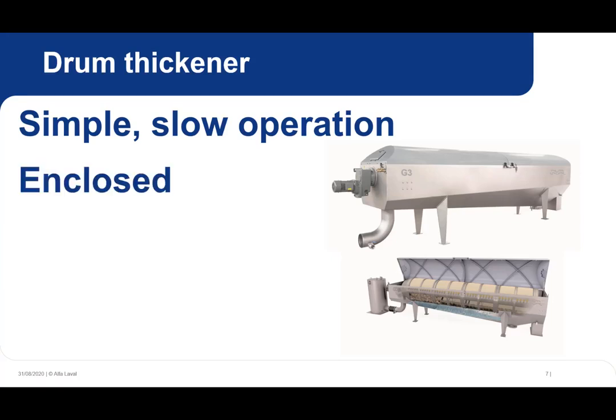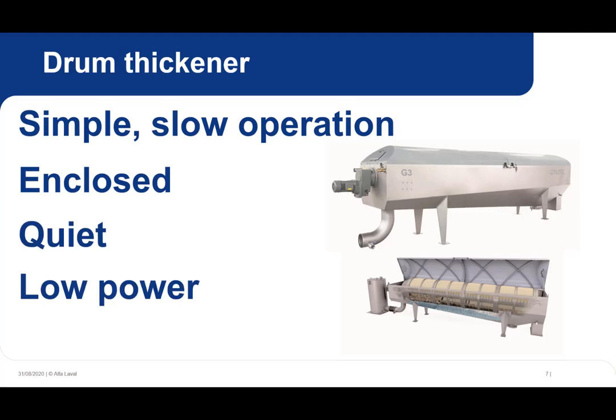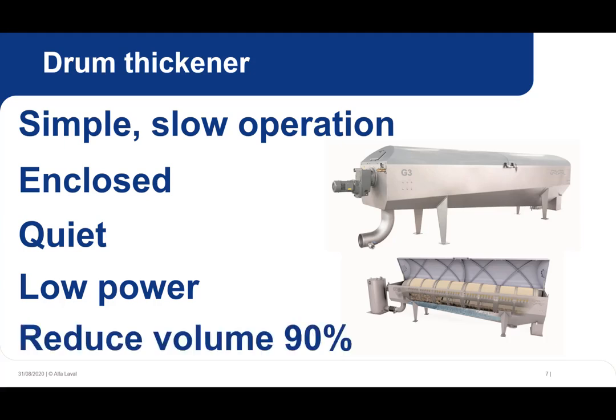A fully enclosed design means that a drum filter will be better at containing odor and can be installed outside if necessary. It runs quietly and has low power requirements. Thickening performance can be adjusted by varying the feed rate, the polymer type and dosage, the drum speed, and the spraying interval. It is possible to achieve up to a 90% reduction in sludge volume with a drum thickener. It has a medium-sized footprint and requires more wash water than, say, a decanter centrifuge would, but is relatively low because it is cleaned intermittently. You'll often see the drum thickener selected when footprint is a consideration and when simple operation or an always enclosed design are desired.